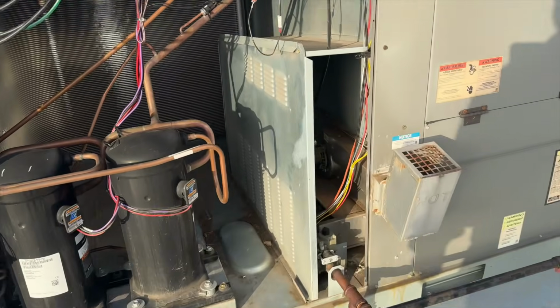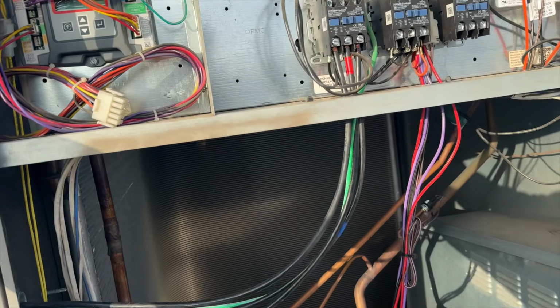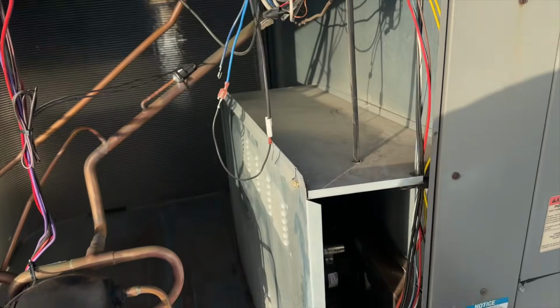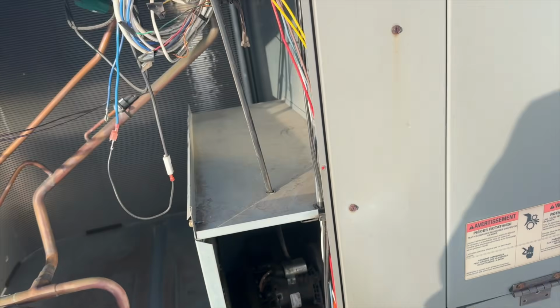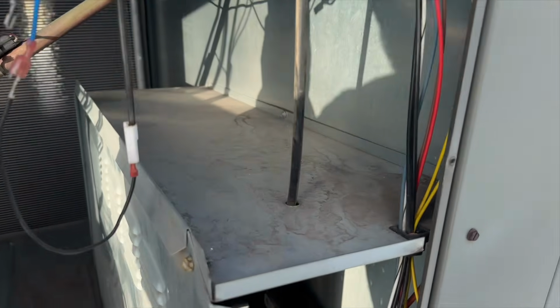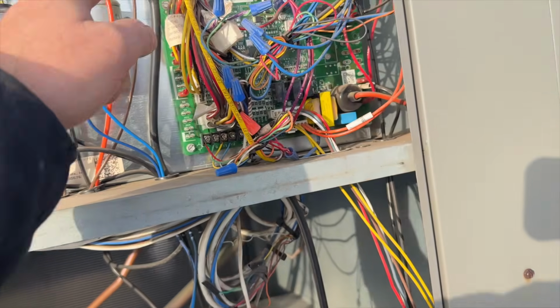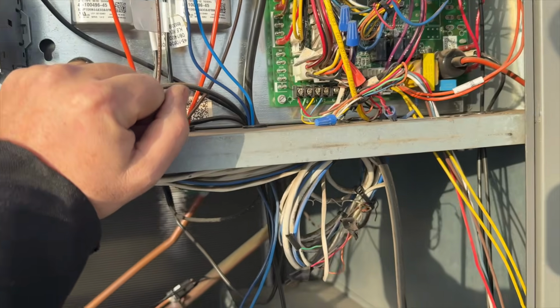Okay, so let's go ahead and reset this bad boy and we'll go from there. So we did see the inducer kick on. So it's saying the pressure switch is not closing, which is right here. Looks like there's only one.